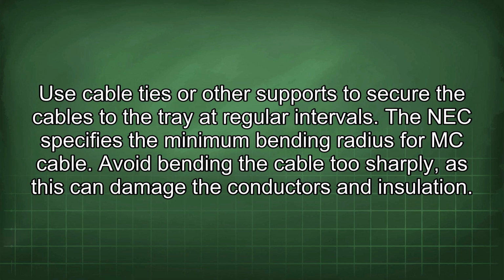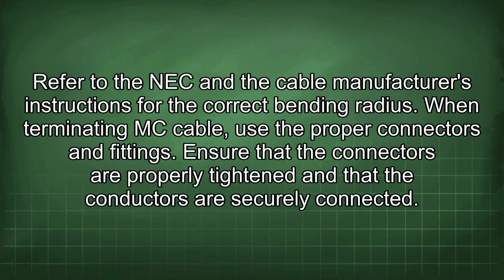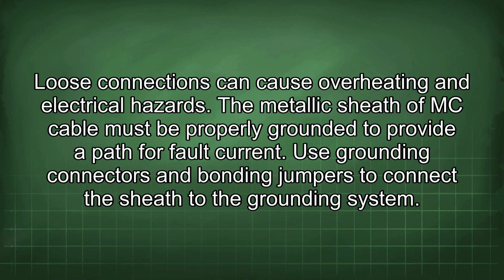The NEC specifies the minimum bending radius for MC cable. Avoid bending the cable too sharply, as this can damage the conductors and insulation. Refer to the NEC and the cable manufacturer's instructions for the correct bending radius. When terminating MC cable, use the proper connectors and fittings. Ensure that the connectors are properly tightened and that the conductors are securely connected. Loose connections can cause overheating and electrical hazards.